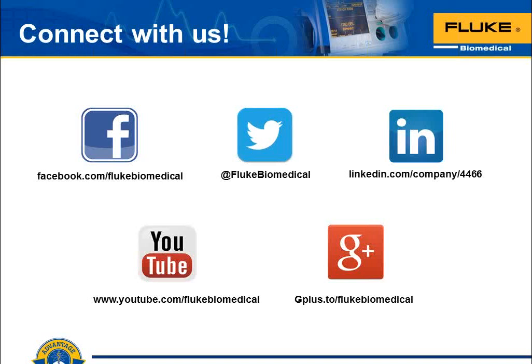Excellent. Okay, here's another one that came in. What about Crest Factors? Do we need to test and record this reading? Yeah, a good electrosurgery unit analyzer is going to report the Crest Factor. There is other training that we have available that identifies what in fact a Crest Factor is. What's the math around getting to a Crest Factor? I'm not going to go into it right now, but that's available, and certainly there are a lot of places that you can find the definition of Crest Factor. But a good electrosurgery unit analyzer is going to provide that for you. It will read out the Crest Factor.